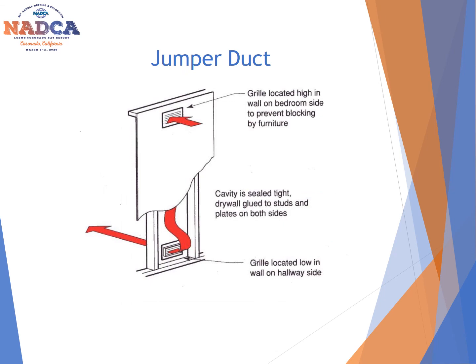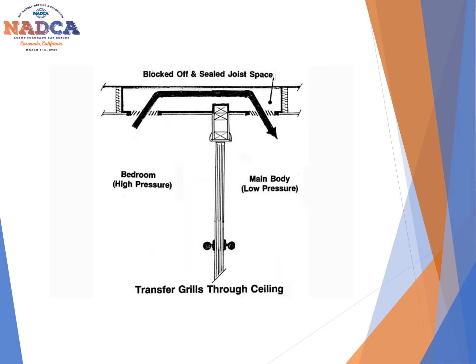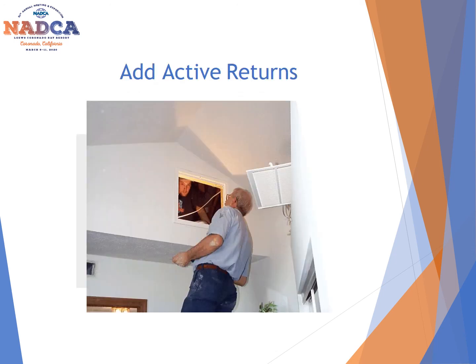Here's another example of a jumper duct where you may have the grill high inside the bedroom, so that can't be blocked by furniture, and then it comes out low on the other side as it flows into the hallway. Now, the way this would have to be set up is the drywall in the cavity itself would have to be completely sealed, including the drywall being glued directly to the wall to make sure you have a good, tight envelope as the air passes through. And then here's just another one where you may actually use the floor joists or the dead air space between the 2 floors to allow the air just to go up and over the wall cavity itself. So in summary, essentially, if you have a situation where you have air that is not flowing easily from one space to another space, utilizing jumper ducts or even utilize active returns, open air return systems can help greatly increase the air pressure and help minimize the hot pockets and cold pockets you may otherwise have in a facility or within a home.